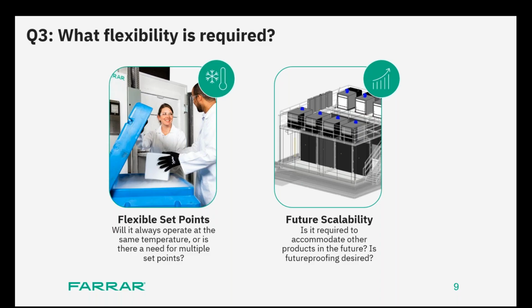Rebecca, you are on point today with these questions. Fantastic question again. So I'm going to answer this question with two subsequent aspects, right? First, flexibility, and then based on that, scalability, right? So if you look at a standard ULT, the working range for the temperature for a standard ULT is somewhere between -50 and -80 degrees C, right? That's basically how it works.